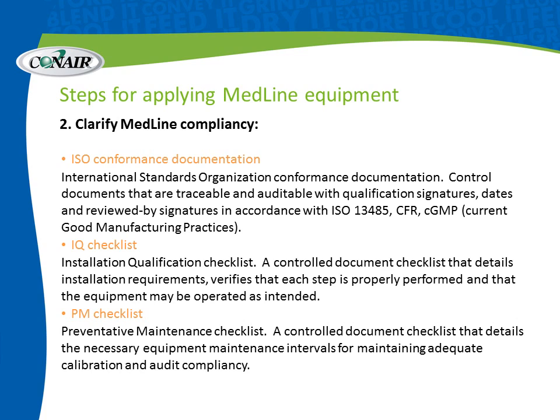Now you can feel free to stop the recording at any time and go through these lists in more detail, and we'll just bounce through this quickly. ISO conformance documentation. ISO drives a lot of the way companies like yours work, and this equipment complies to that exactly. The IQ checklist. This is an installation qualification checklist. This is produced by Conair and included with every piece of equipment to make sure that it is installed correctly.